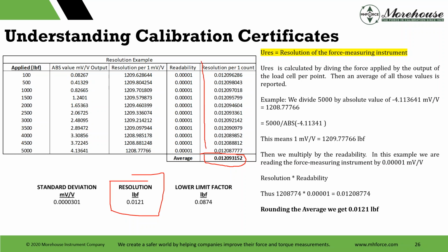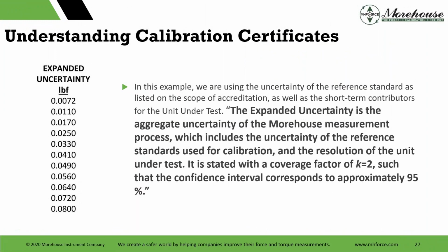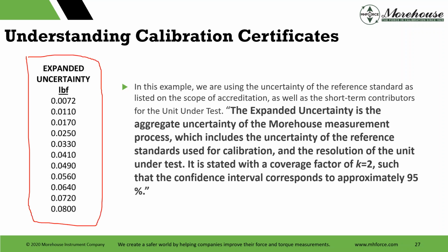But if we look at this in a lot more detail here, you can see resolution per count is changing, 090909, there's 080808. It's really close. Though rounding the average, we still get the same answer here. So just something to look at. Then expanded uncertainty. In this example, we're using the uncertainty of the reference standard as listed on the scope of accreditation, as well as the short-term contributors for the unit under test. I read this earlier, the expanded uncertainty is aggregate. So here we're looking at expanded uncertainty, what's included, and we have to state that at a confidence interval that corresponds to roughly 95%.